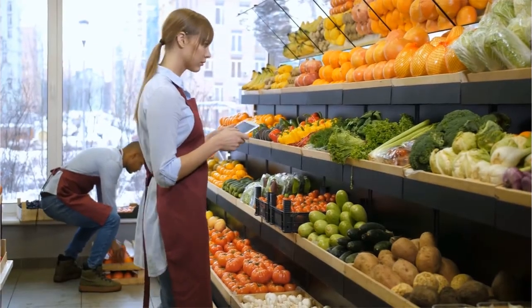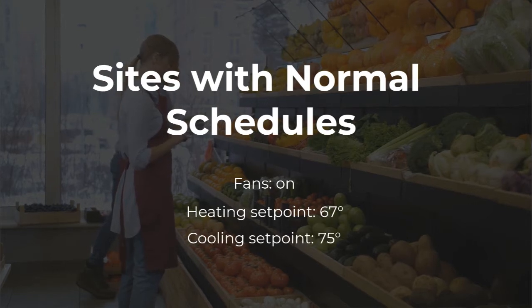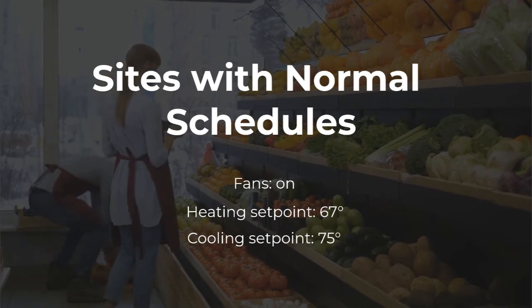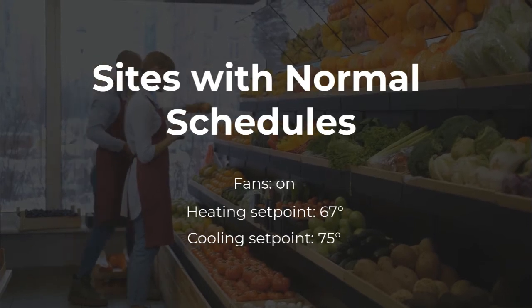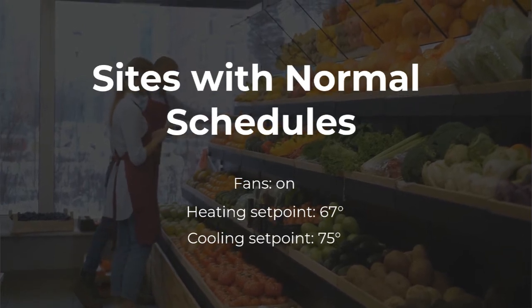If your business is up and running normally, there's still opportunity to adjust set points for savings. During occupied times, turn fans on. And if the HVAC is calling for heat, we recommend lowering the set point to 67 degrees. If the HVAC is cooling, we recommend raising it to 75 degrees. We've found these set points to be the best balance for comfort and savings. You can work with your EMS provider to identify periods throughout the day where HVAC energy can be cut back to maximize savings even more.